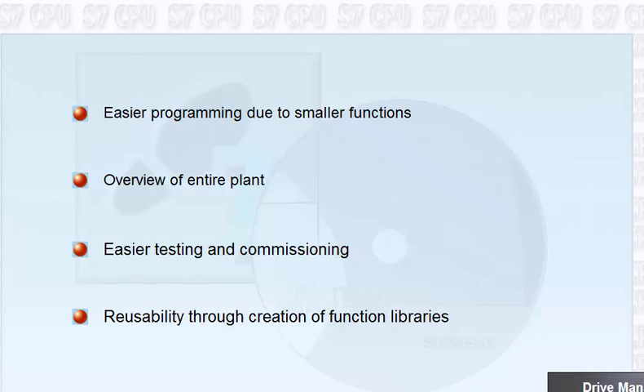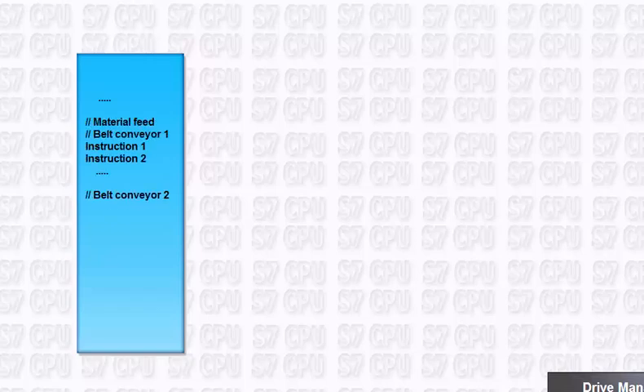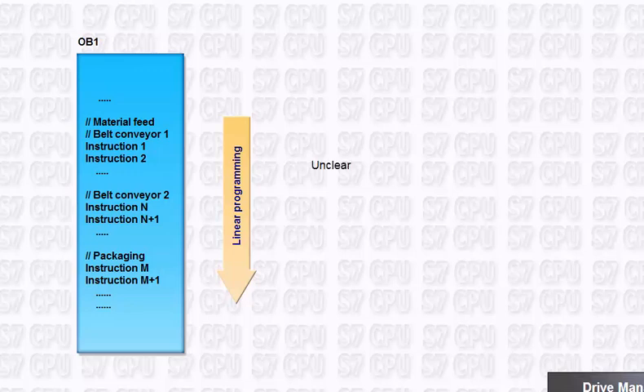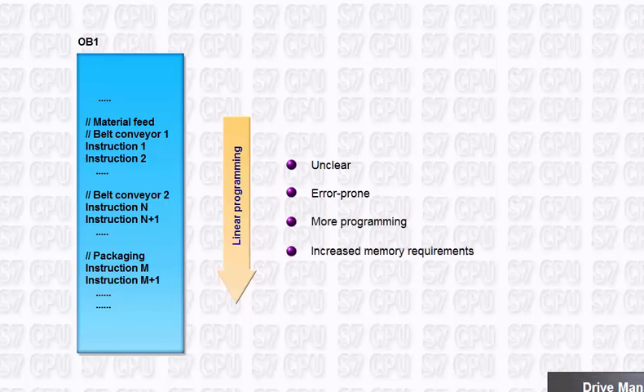Let us take a closer look at an example taken from a possible realization of this plant structure. In principle, an entire program can be instruction by instruction contained in one single block, for example the organization block OB1. This is referred to as a linear program. This type of programming, however, has the disadvantage of not being clear, hence prone to errors, huge programming requirements, and increased memory requirements.